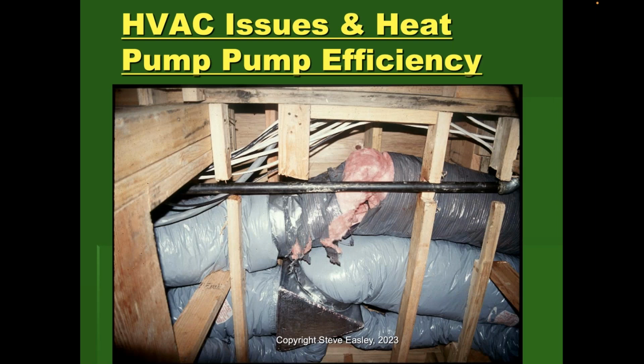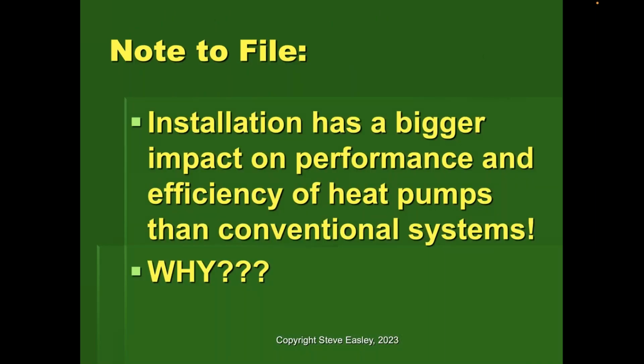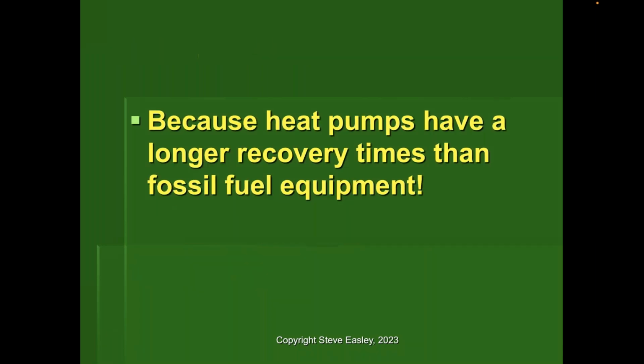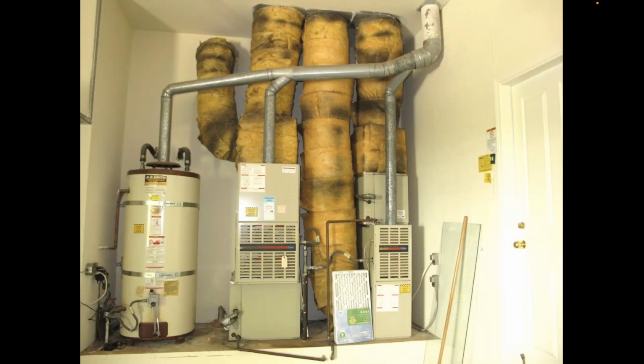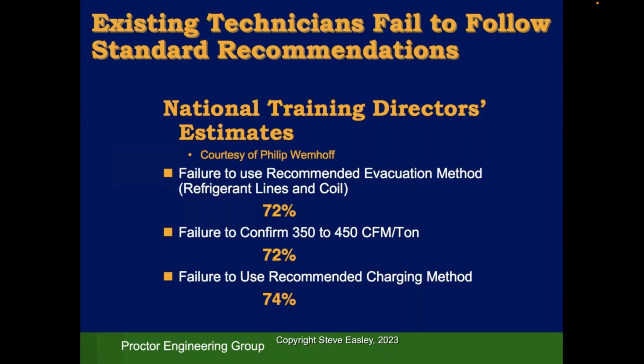When you look at these distribution systems, one of the reasons why we switched from the old system of SEER and HSPF to SEER2, EER2 and HSPF2 is because this is the type of thing we saw in these systems. And so the installation has a much bigger impact on performance for heat pumps than it does for conventional systems. Why? It's just because heat pumps simply have to take the heat out of the air, so they have to work a little longer than their dinosaur burner counterparts. Well, that's why we pay attention to those installation details.